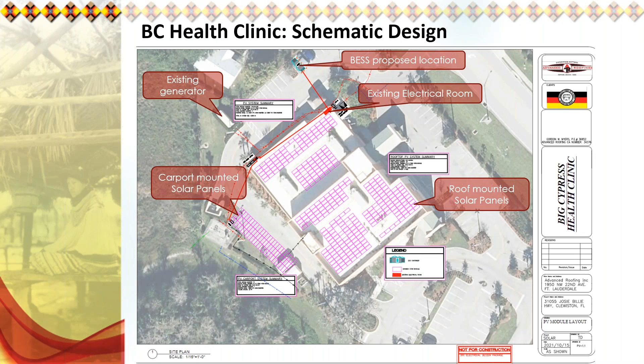Next slide, please. This here is a design logic diagram, which I will not go into, but when we received the 30% design from AGT, we looked at this logic diagram, and basically what this is telling me is that in the event the grid goes down, the battery is going to run the building for about 3 hours. When it's depleted to a certain level, the generator will kick in and run the facility. However, during this operation, the BESS will continue to supplement the generator to reduce the load on it. But in this scenario, the generator would have to continue to run incessantly, and that is not what we were looking for.